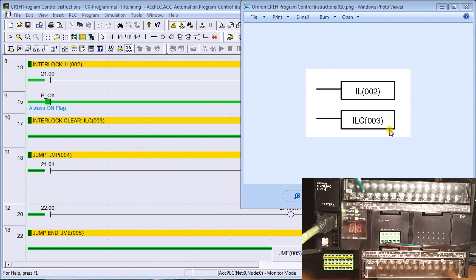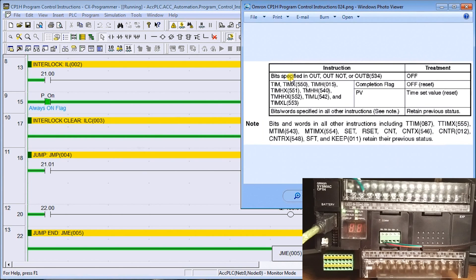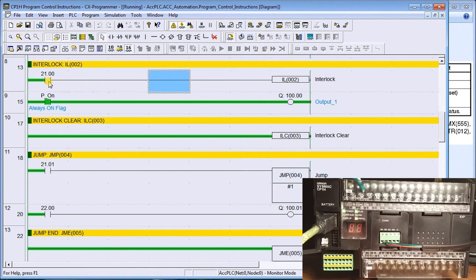Interlock and interlock clear are very common in a lot of programs. When the condition is on, we have normal execution and whatever's in here gets scanned normally. When the condition becomes off, the outputs are interlocked — meaning they turn off. The bit status of each output turns off, and the timers get reset; the time set value is reset on timers. That's exactly how the interlock works.